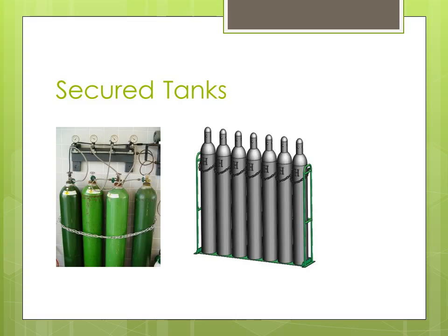Something else to keep in mind is that when you're transporting tanks, there is a tendency to want to lay tanks down, like in the back of a van. Well, technically you're not allowed to do that. You need to secure them in an upright position when you transport them. I think that's another common practice that people don't realize violates codes. So that's it for medical gas and our overview.